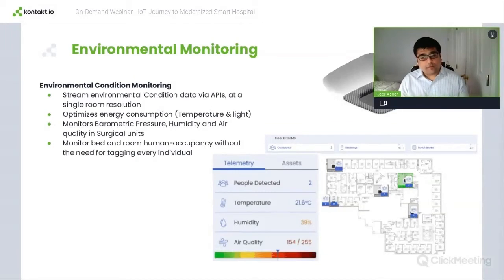On top of that, this is also an IR beacon and a BLE beacon. So it floods the entire room with infrared. And if you remember, I was talking about the asset tag and the staff tag having an IR sensor. When these tags come inside the room, they sense the IR from the portal beam, and that IR uniquely identifies that room. Because IR cannot penetrate through walls, the location of those tags is contained within the four walls of that room. And that's how we achieve room level.